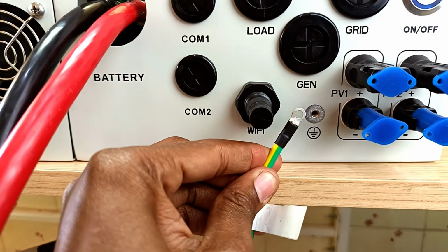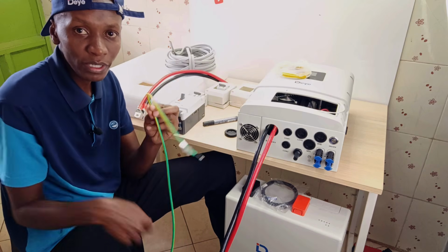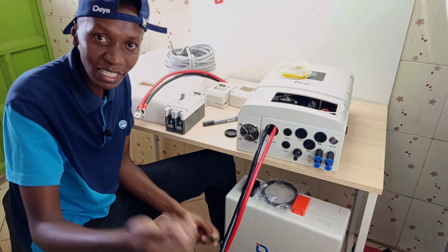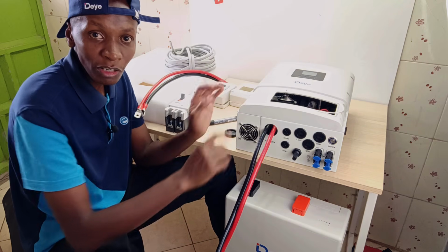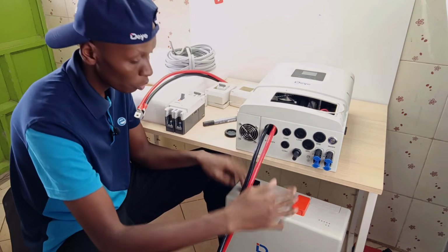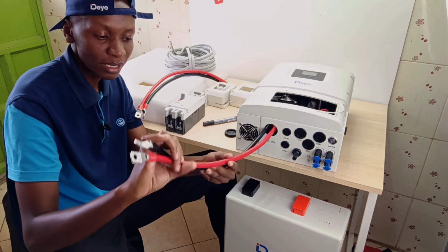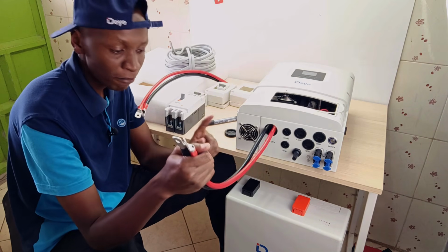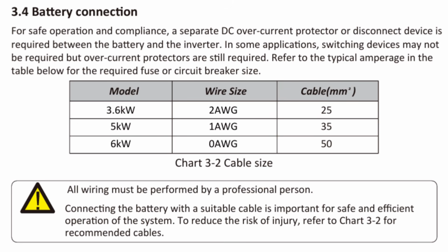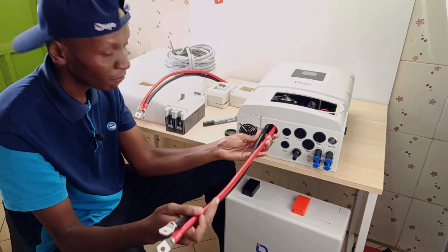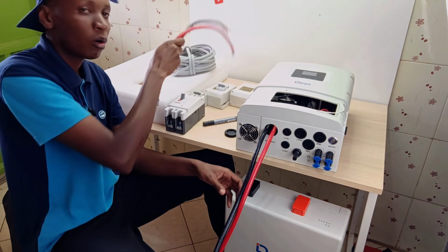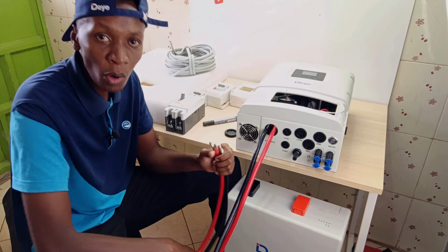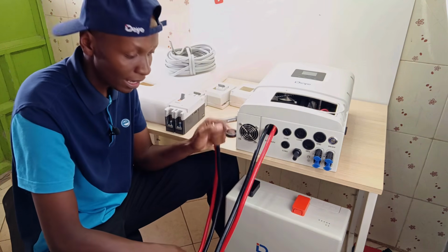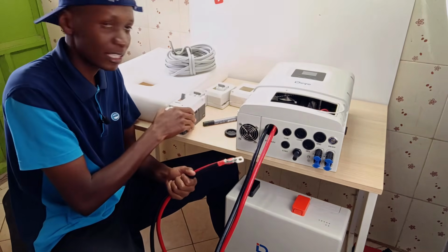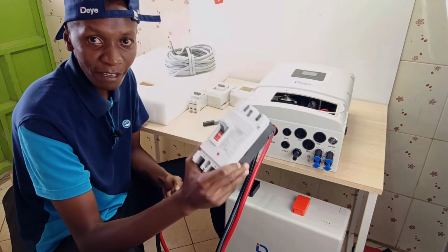Another very important thing, the protective earth cable. You should always connect this cable between your battery and your inverter. The inverter connection is here and the battery connection is here. According to the inverter manual, you're supposed to connect the inverter to the battery using 50mm square cables. 50mm square is the cross-sectional area of the conductor inside, and that's what I have here. Very thick cables. I was just testing if they fit inside here. Now, also according to the manual, you're supposed to connect a 200 amp DC breaker between the inverter and the battery. And this is what I've bought. This breaker didn't come with the inverter or the battery.